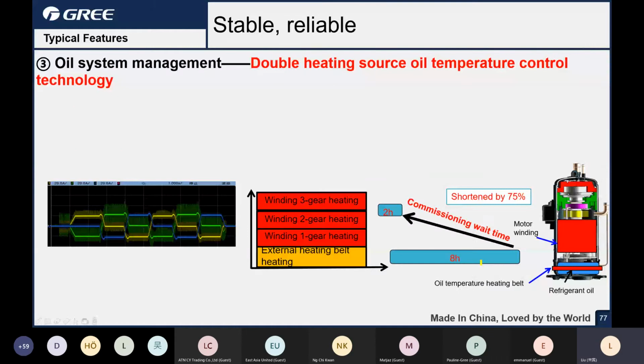Next one is about the oil system. For VRF units, it needs to do the preheating, right? Lots of people, they have a headache about the preheating. They think the 8 hours is too long to wait. So in GMV6, we changed some design. For the previous generation, we use the heating belt on the compressor to do the heating, just the one heating belt. So the power maybe not very big. It needs 8 hours to finish the preheating.